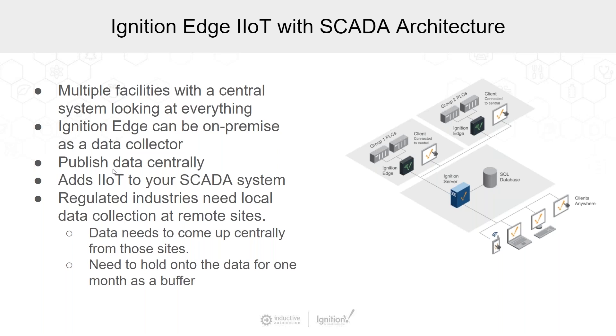This really helps solve one of the hurdles you see in regulated industries like oil and gas or water and wastewater, where collecting and storing data on-site is not just a nice-to-have — it may be dictated by regulations and laws. A lot of those have regulations about having up to a one-month data buffer, and that was a big motivation for us to increase from the seven-day buffer.